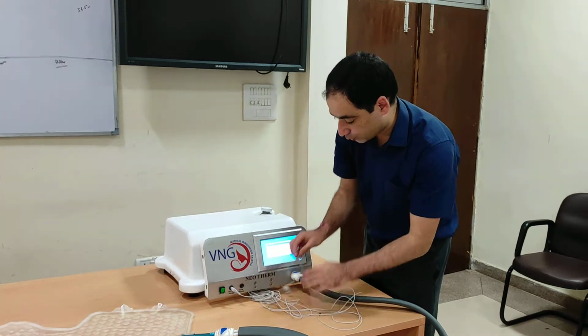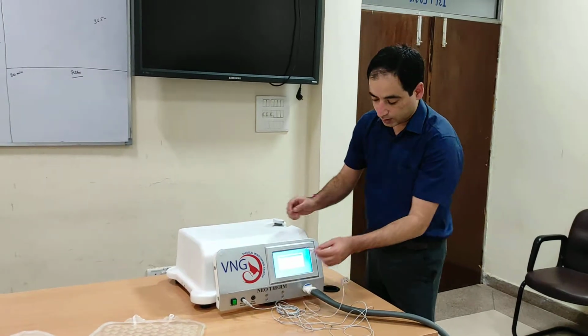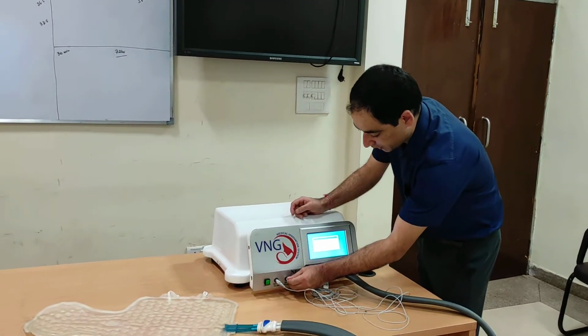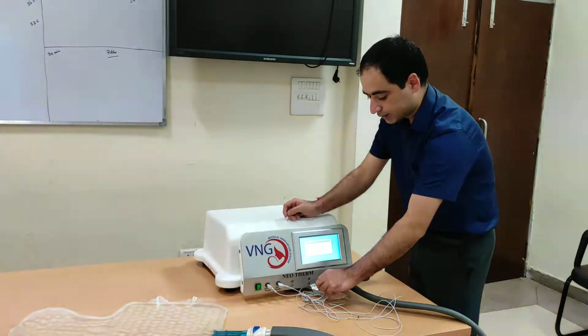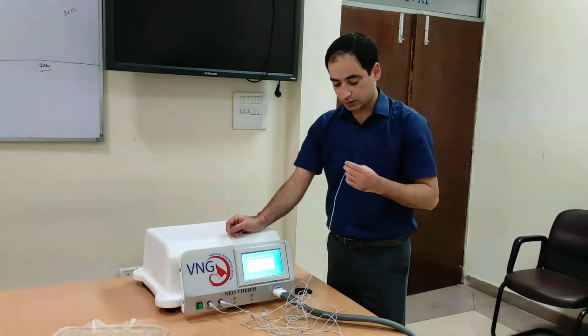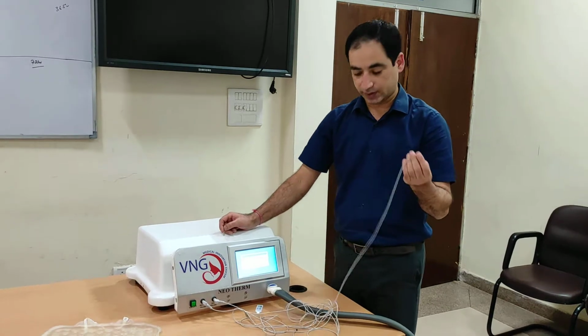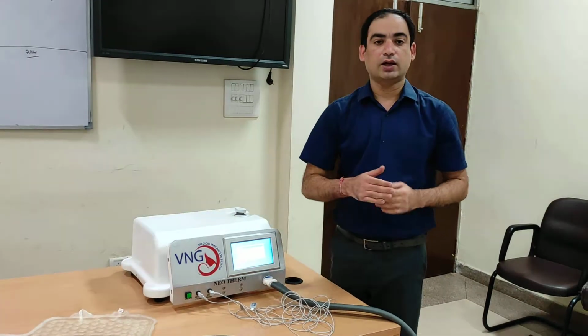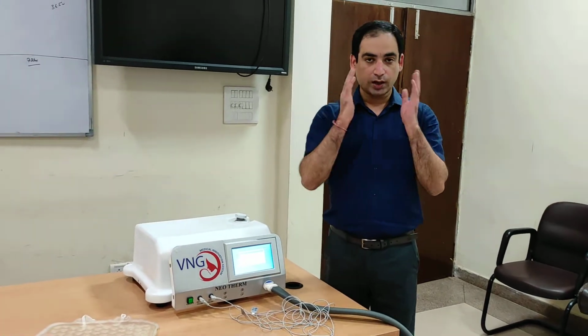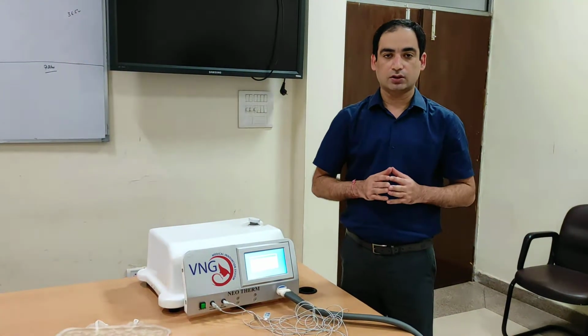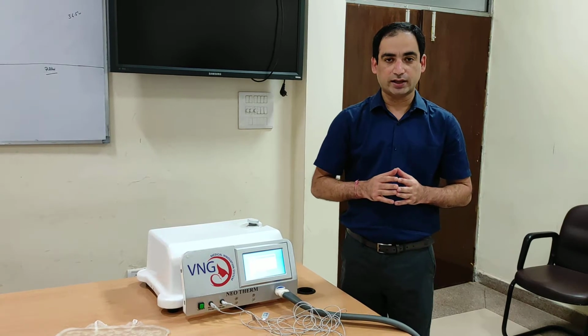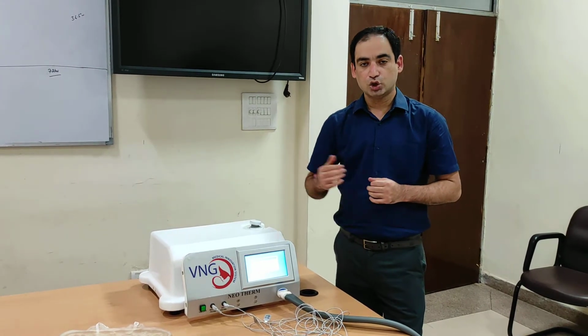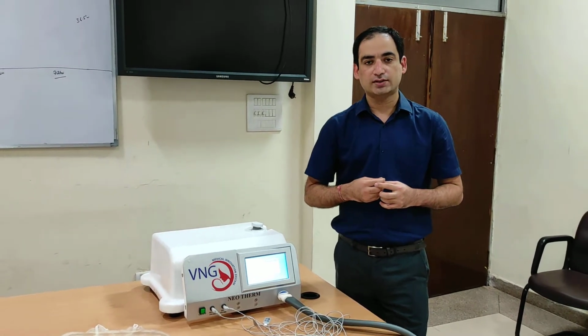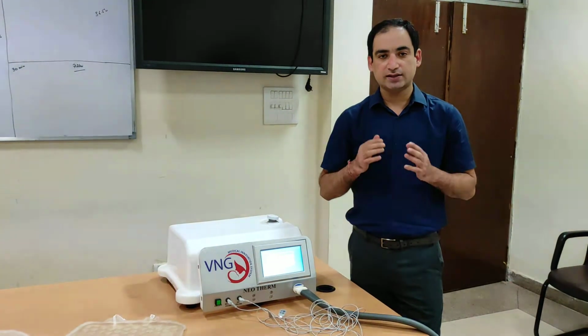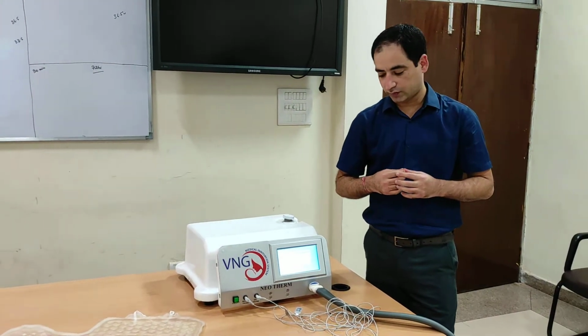Then we have another probe, that is the skin probe. Again, it has to be fitted to the main machine, and then the other end can be placed on the skin to display skin temperature. Remember that throughout the therapy, our main focus is on the core temperature, that is the rectal temperature. So you should always concentrate on rectal temperature, and our target usually in whole body cooling is around 33.5. That is, the set temperature has to be 33.5.